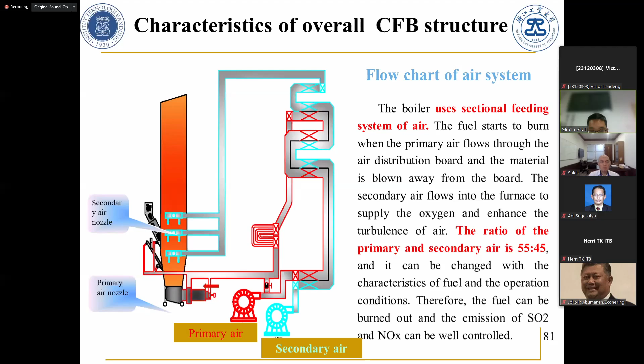The main points for the key design of a CFB boiler: first is how to ensure the ignition of waste. That means we should burn it and maintain the high temperature of the boiler. As mentioned, in the standard regulation, we have to make the flue gas stay more than 2 seconds over 850 centigrade. The second is how to ensure the burnout of the waste and to meet the pollutant discharge standard, because the emission is related to incomplete combustion. So it is very important. Ensuring burnout of the waste means the ignition loss of the slag should be less than 5% for the standard. Usually the factory will set the target at 3%.